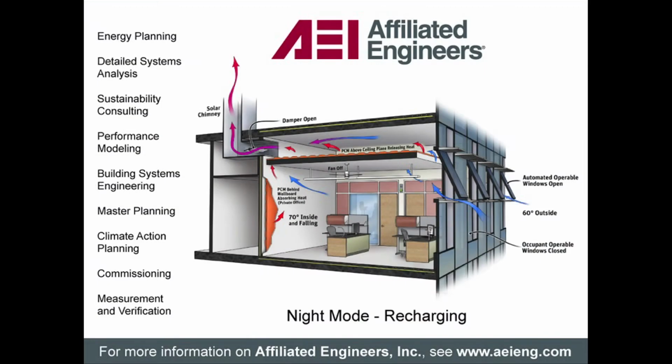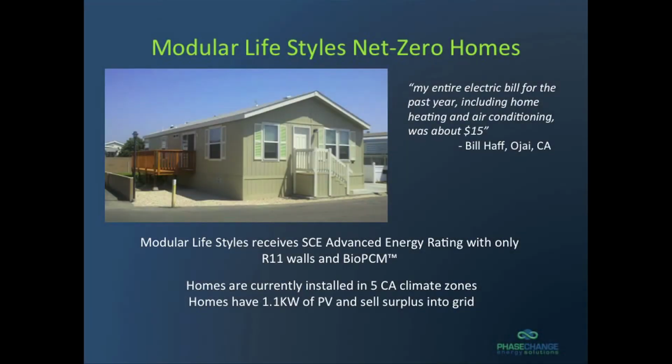This is probably our biggest project, University of Washington, a 90,000 square foot building with no air conditioning, all with phase change. So we put the phase change just above the 2x4 ceiling tile. Energy heats up, phase change holds the heat, and then at nighttime these windows open up, takes the cool air from the top, runs it over the phase change, pulls the energy out of the phase change and up to a solar chimney. So they're doing a whole building without air conditioning. Very small modular net zero homes. We got this home wrapped in phase change.